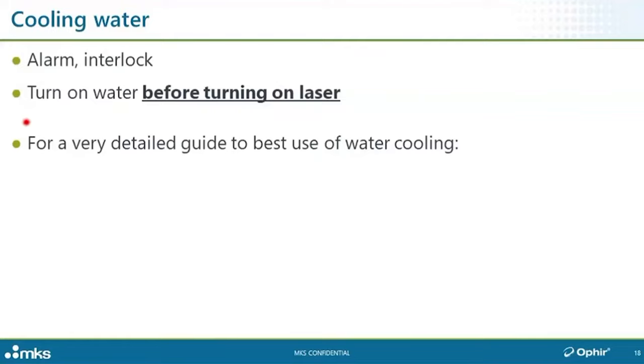A very, very important point: you have your high power laser, your cooling water system, and your sensor all set up. Turn on the cooling water before you turn on the laser. Those few seconds in which there's no cooling water but 16 kilowatts of power are blasting into your sensor can do a lot of damage. You'd be surprised how often we get damaged sensors coming in for repair from seasoned laser professionals — it's easy to overlook. There's an excellent white paper on our website titled 'How to Use Water-Cooled Ophir Sensors' covering flow conditions, flow rate, pressure drop, water inlet temperature range, and corrosion additives.